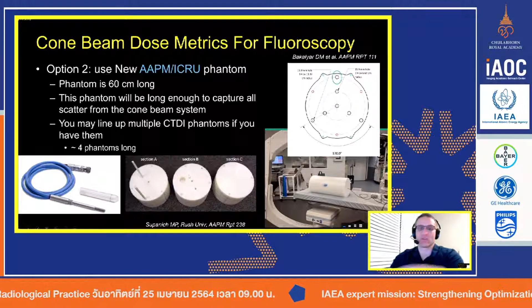Well, the idea here is if you were to place your ion chamber at the center and you turned on this beam and you did your spin, and you collected all your radiation, you're going to get a bunch of scatter. And so we need to collect all of this scatter data. Now, once again, we don't have an ion chamber that's 600 millimeters long. You just can't go buy one of those.